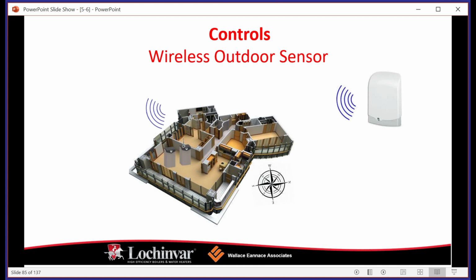Okay, so when we install the outdoor air temperature sensor, we can tell the boiler that it is 25 degrees outside, it's very cold, we need to heat the space, and the boiler is going to take that information, and again, running algorithms based on its inlet and outlet temperature, it's going to run at a higher fire rate, because at that point, the boiler is going to calculate that it needs more energy to satisfy our requirements for our space heating. As that outdoor air temperature begins to increase, it's going to read the outdoor air temperature, and then conversely, it's going to say, I don't need as much heat.